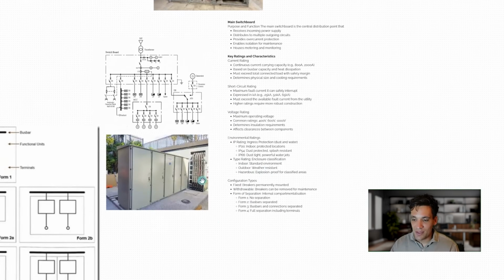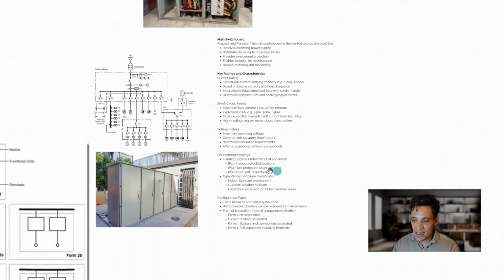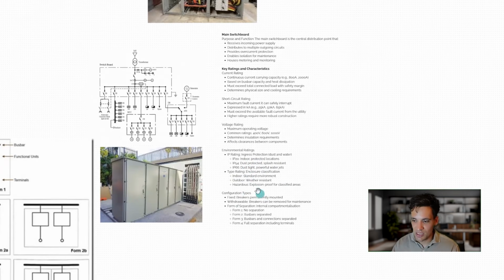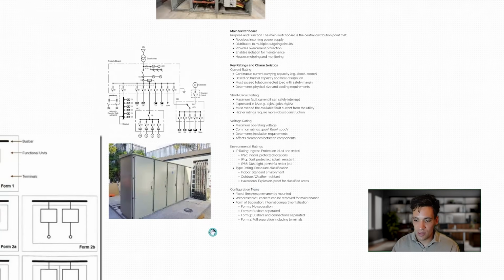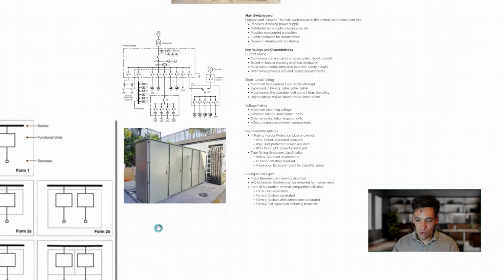Main switchboards also have different environmental ratings. If you're installing a main switchboard in a building, in a controlled environment where there's not a lot of dust, you might have an indoor level of protection. The level of protection is referred to as an IP rating, which is short for ingress protection. So IP20 could be used for indoor protected locations, while you might have IP66, which is dust tight and you can spray water on it so it's protected from rain and dust, which might be a board like this, installed outside. The main switchboard can also have different configuration types. You could have fixed breakers that are permanently mounted, or you could have withdrawable breakers where you could withdraw the circuit breaker while it's still in operation.